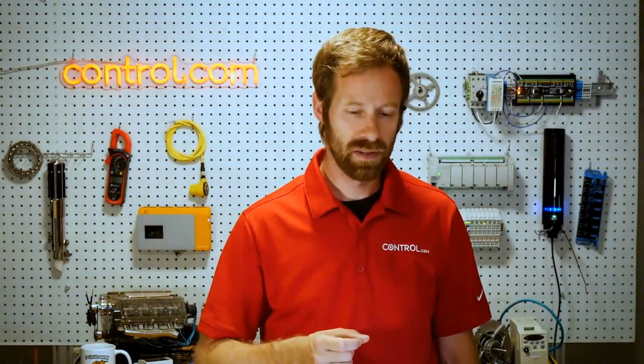Do we want to track data for a process? Or do we want to track data over a long period of time to tell us what might be happening, what might be deviating from a normal thing? Let's take an example of a box on a conveyor belt. Now the sensor is supposed to trip every time a box goes past on a conveyor belt. Well, we could use a discrete sensor for that. It's easy. We just make the adjustment to the right point, and the sensor is going to trip every time a box goes past.